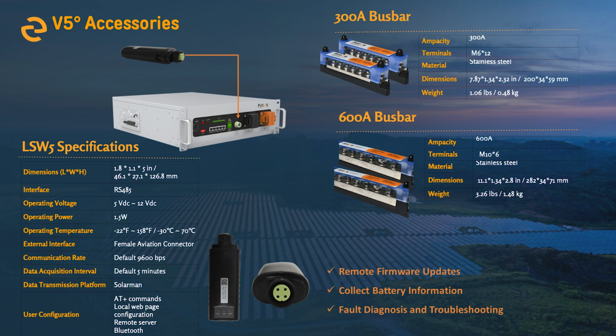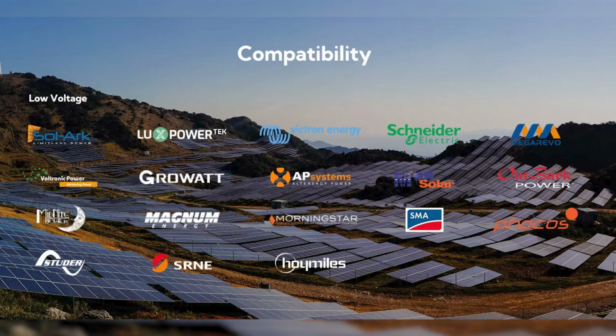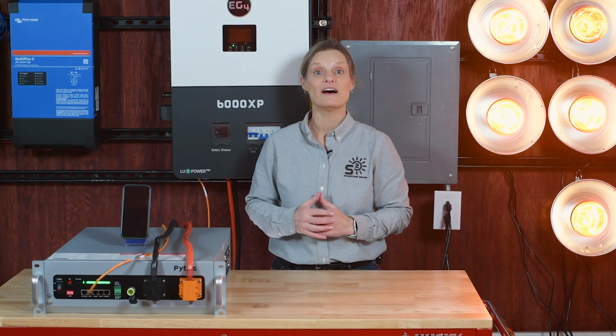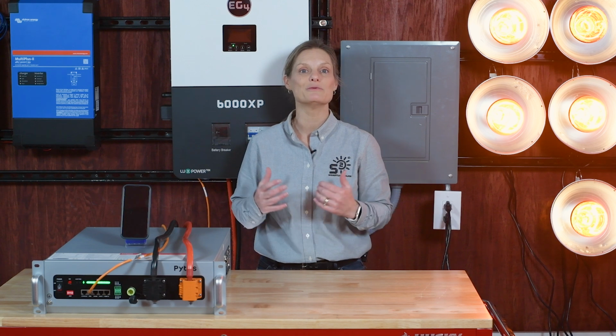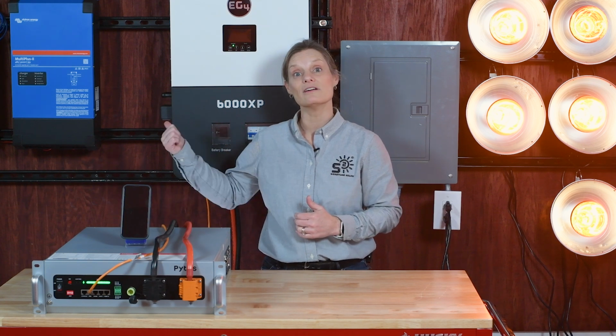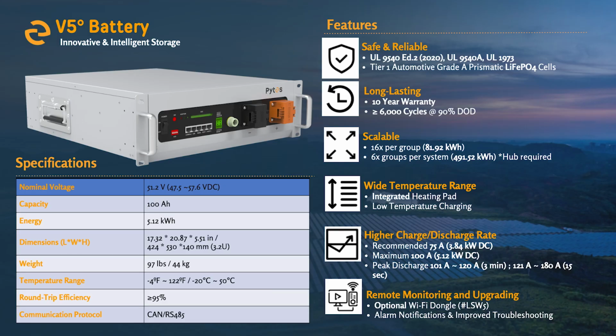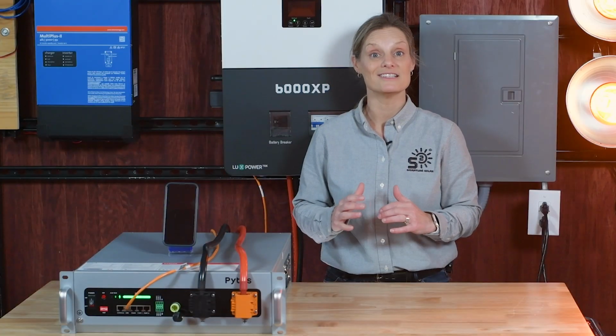The improved busbar connections and new design make wiring straightforward, reducing the clutter and potential points of failure. Compatibility is a key consideration when choosing a battery, and Pytes has you covered. The V5 communicates via RS-485 and CAN, enabling closed-loop communication with popular brands like EG4, Victron, Growatt, and many others. Closed-loop communication ensures that the entire system works seamlessly, with battery and inverter constantly talking to each other to optimize performance.